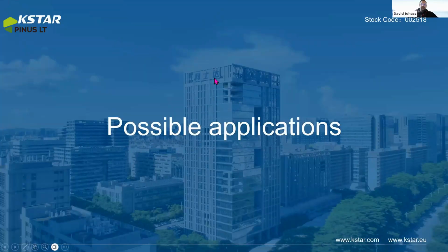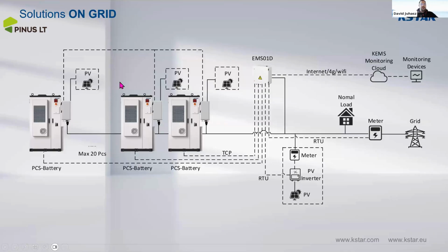I will show the possible applications regarding these solutions. So let's talk first about the on-grid solution. We can use a maximum of 20 pieces of this equipment in parallel. Each of them has a battery and a hybrid inverter, which can have PV connected to it. This can go up to 20 pieces, and each of them should be connected to this EMS01D KSTAR industrial controlling box, which makes it possible for all the equipment to work in one system. This is for the on-grid solution.